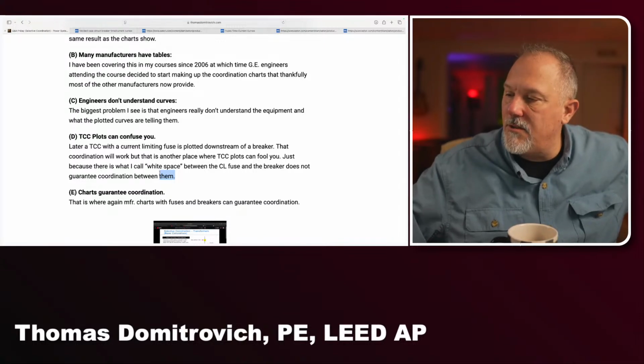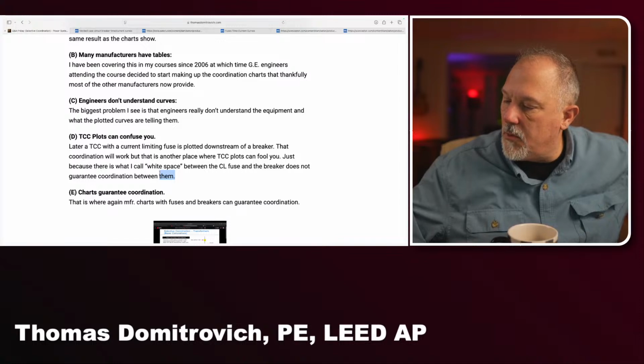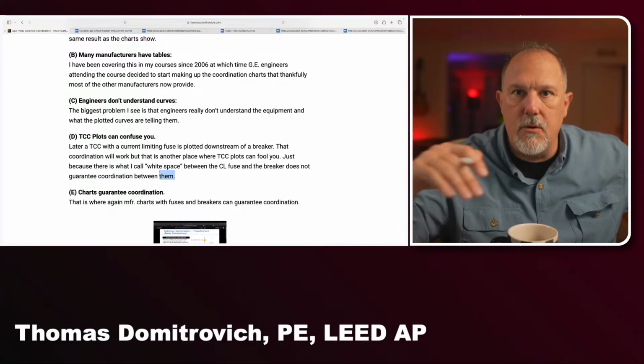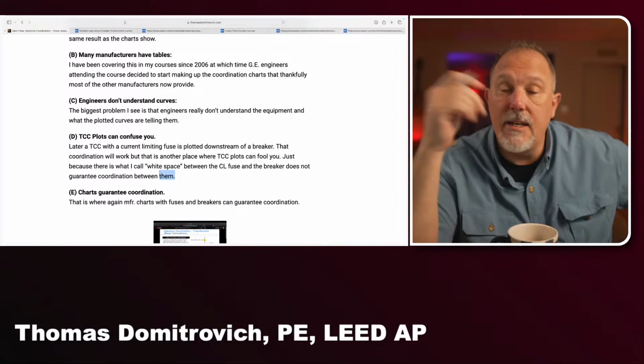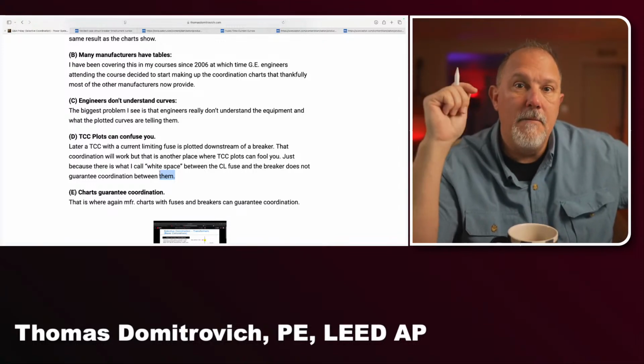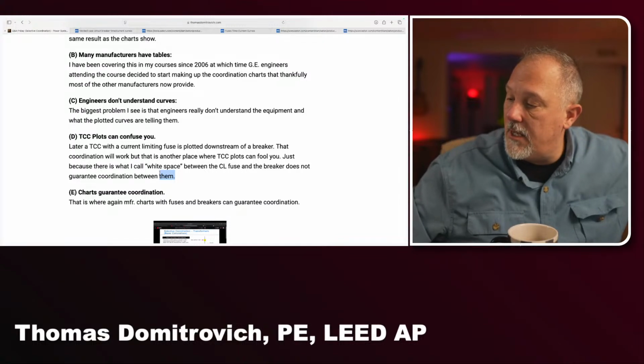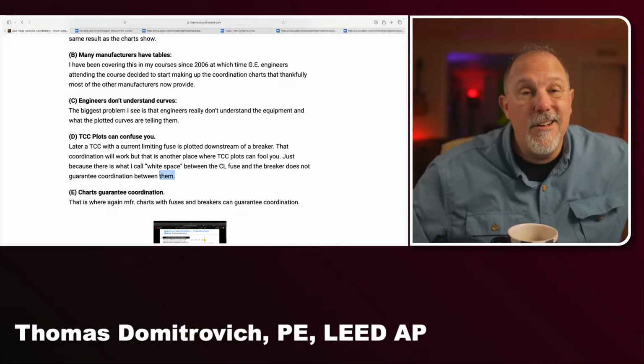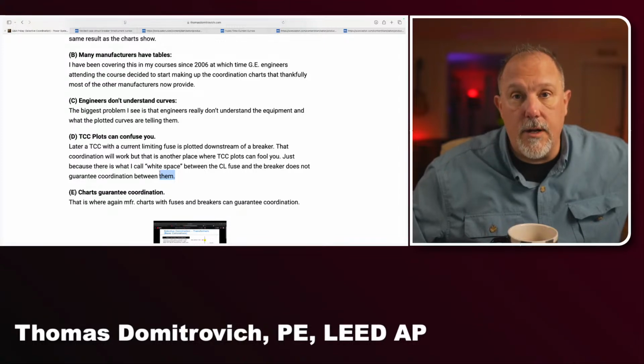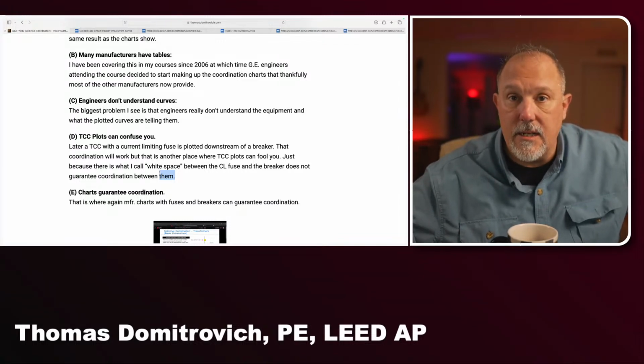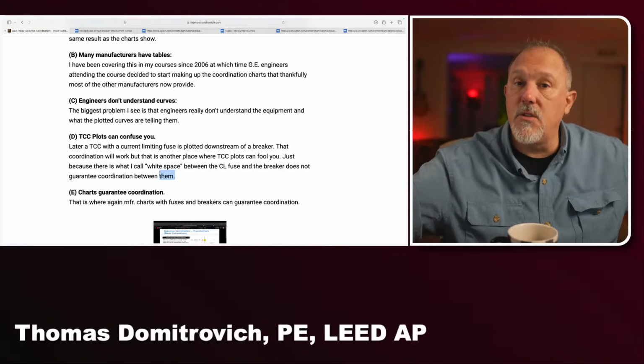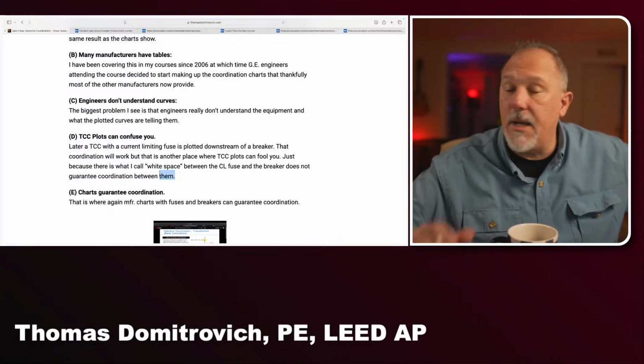We would get that downstream fuse as close to this point as we could get it, somewhere in this area, and before it starts encroaching in on that breaker, and we would put it in a lab and it would work every time. So that was Vince Saporita who did most of that testing, and one of his takeaways was, look, he can get pretty daggone close as long as he gets that fuse as close to that shoe as possible, but not encroaching over it. When we put it in a lab, it worked. Now, it worked for all of the Eaton breakers that we tested. Will it work for every Square D breaker, GE breaker, Siemens breaker? I don't know. But it was a good rule of thumb.